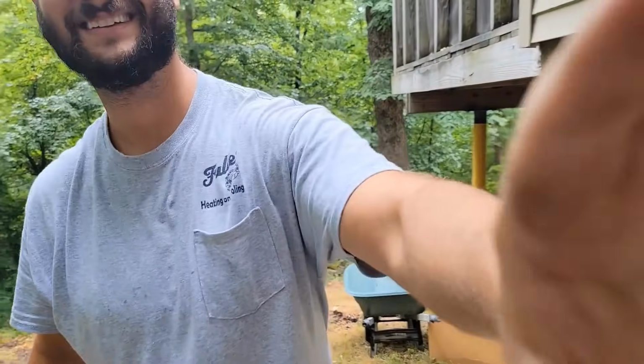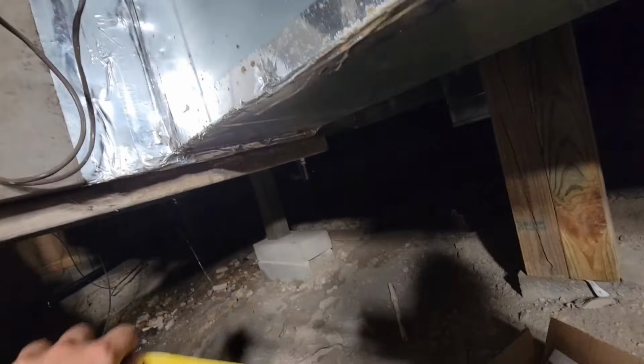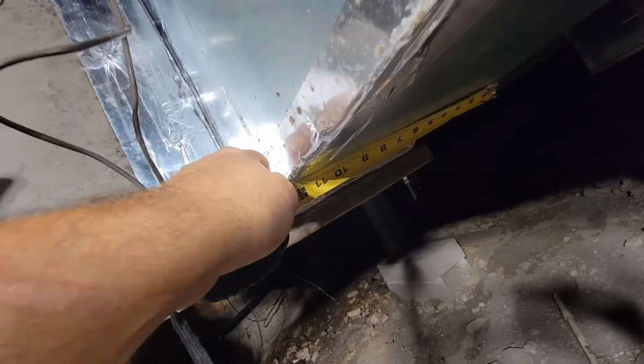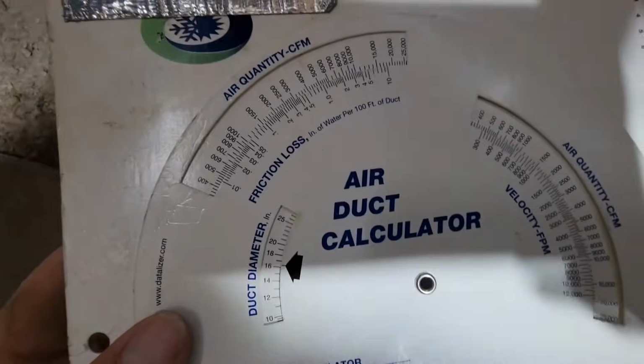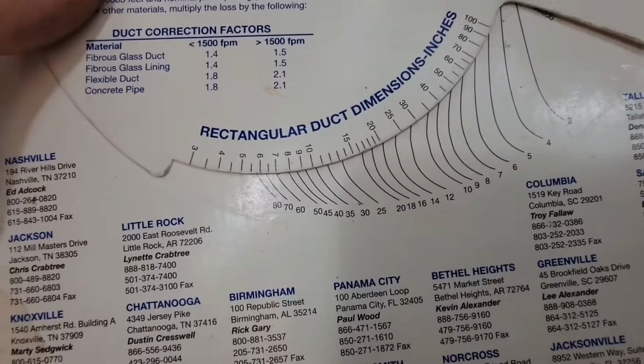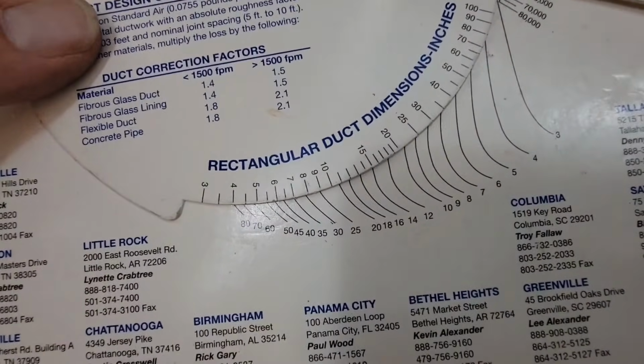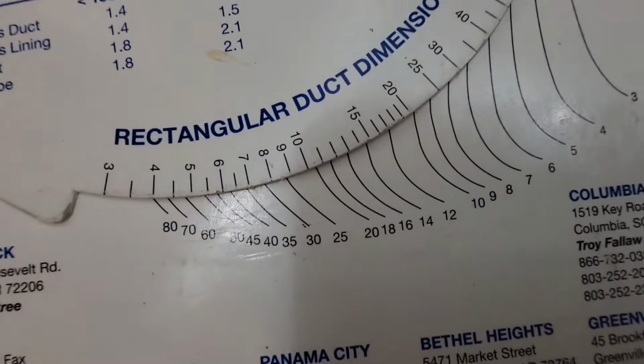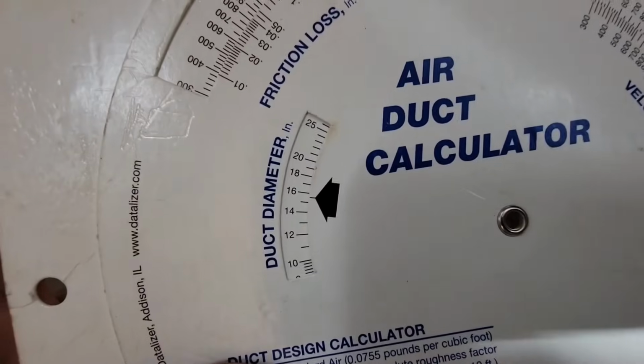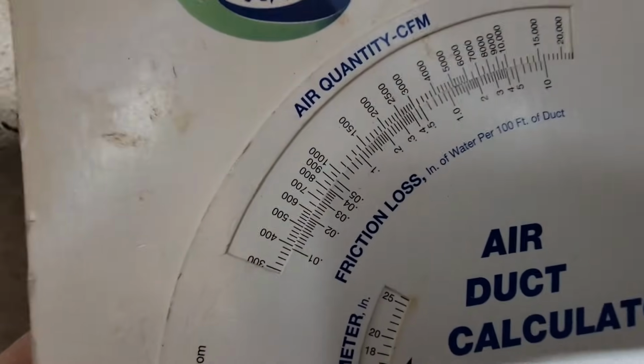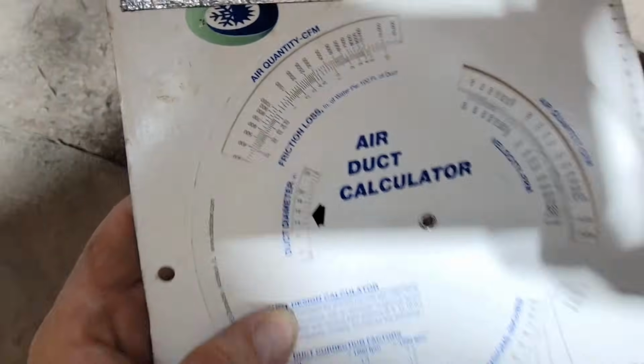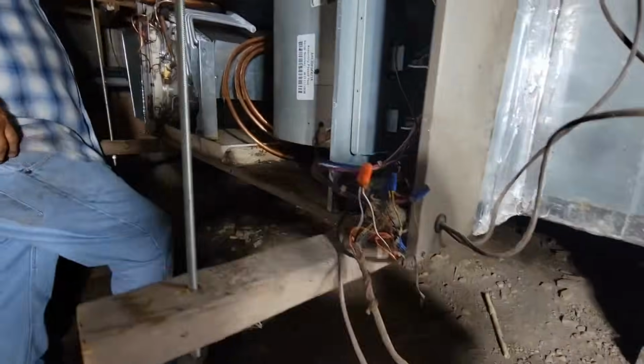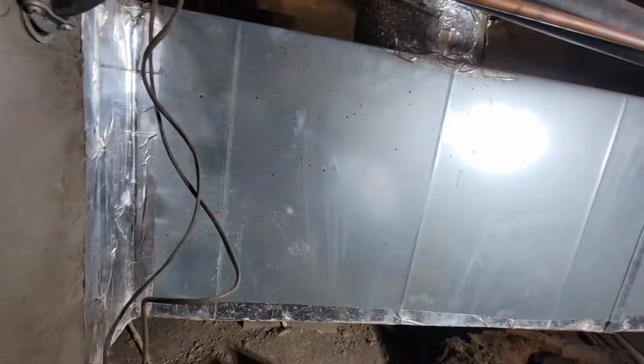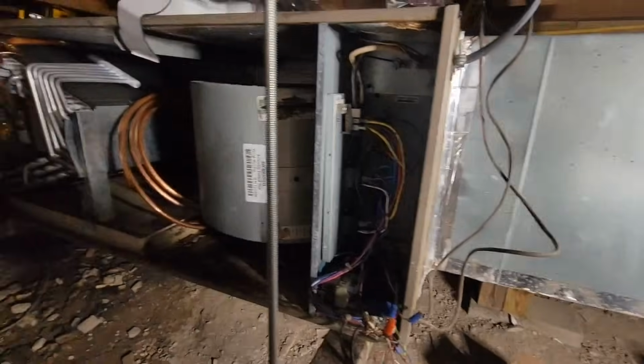Back in the ductwork in my ductulator, we got 17 inches. And let's see, what is this? 17 and 12. Let's check the ductulator here. Ductulator says that 17 and 12 is right there. Line up the 17 with the 12. It says it's equivalent to about a 16 inch duct, 0.05, 900 CFM. So we got a 2-ton unit rated for 800 CFM that we're putting in. So this ductwork is gonna be just right for this 2-ton unit.